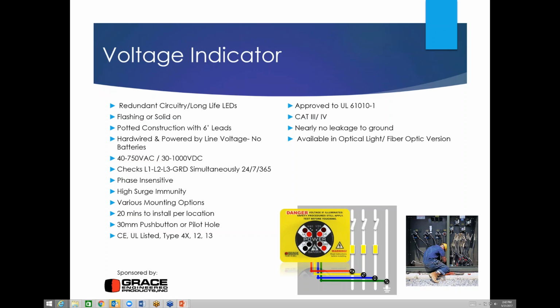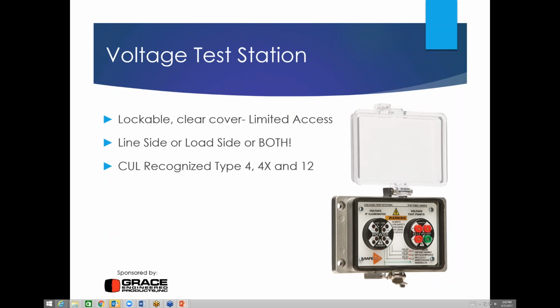So what we do is we take that voltage indicator and marry it with the voltage test point, which we had talked about earlier, and we put that under a clear lockable cover so you can see that the voltage is present, keep non-authorized people outside of the equipment, and then only those that are authorized are able to open the equipment and perform their lockout tagout procedure.